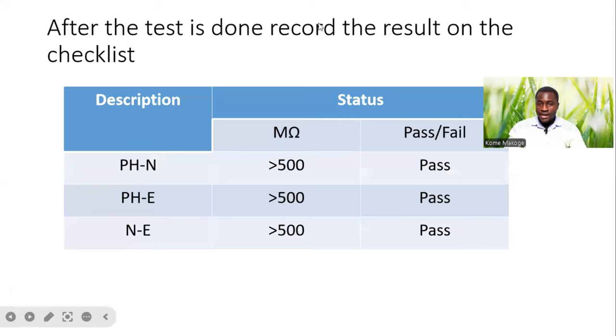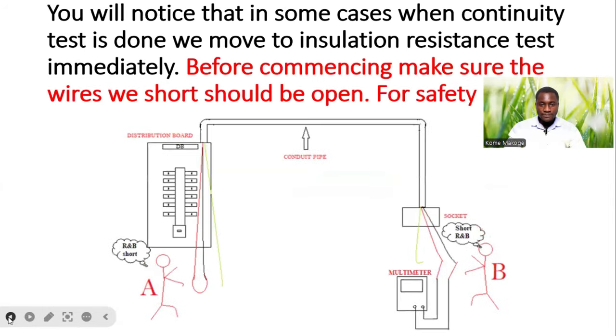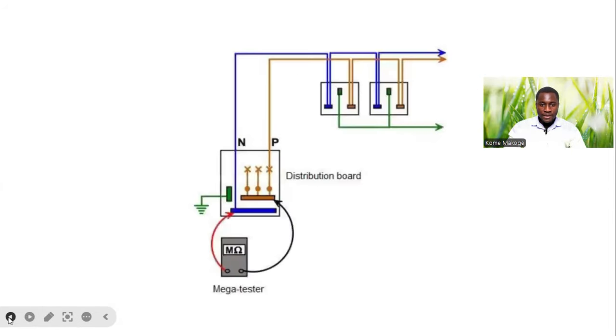After the test is carried out, we record our values and put the status — pass or fail. In this case, the pass result is 500 megaohms or greater than 500 megaohms between phase and neutral, between phase and earth, and between neutral and earth.